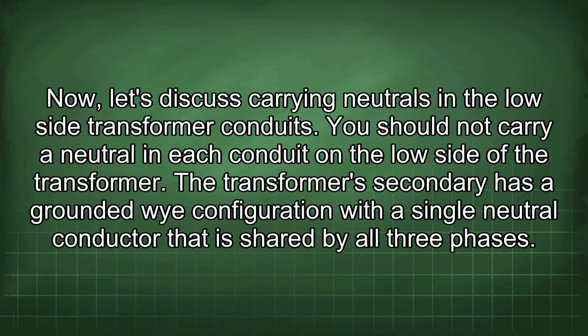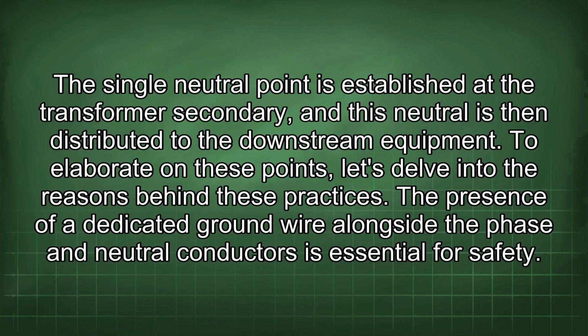Now let's discuss carrying neutrals in the low-side transformer conduits. You should not carry a neutral in each conduit in the low side of the transformer. The transformer's secondary has a grounded Y configuration with a single neutral conductor that is shared by all 3 phases. The single neutral point is established at the transformer secondary, and this neutral is then distributed to the downstream equipment. To elaborate on these points, let's delve into the reasons behind these practices.